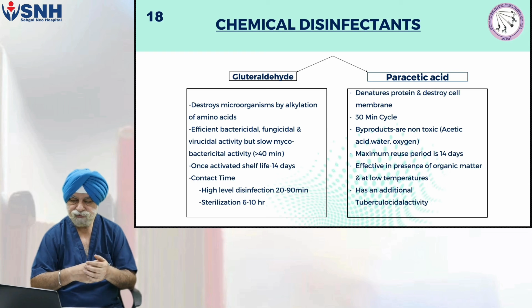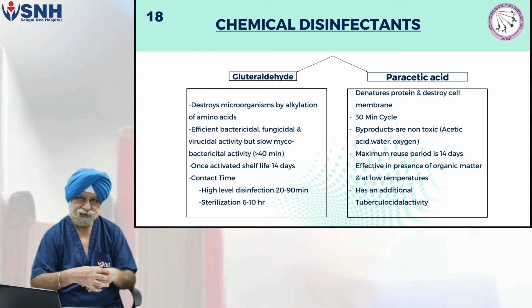Another chemical which is used is peracetic acid. The mechanism by which it does the sterilization is by denaturing the proteins of the microorganism and destroying the cell membrane. One cycle is of a 30-minute duration, and the byproducts are non-toxic: acetic acid and water. Here also the maximum reuse time is 14 days or 14 uses, whichever is earlier. It is also effective in the presence of organic matter, and it can be used at a low temperature. It also has additional tuberculocidal activity. So peracetic acid can also be used.